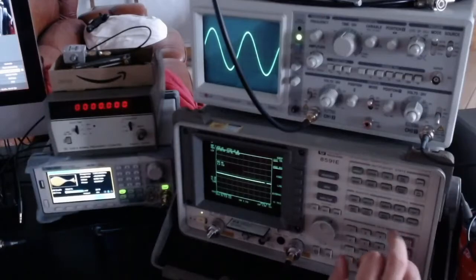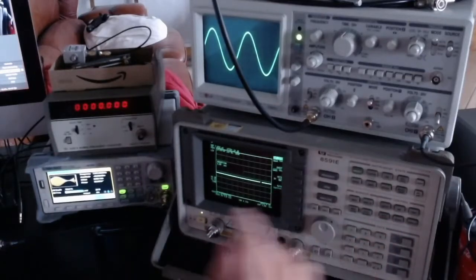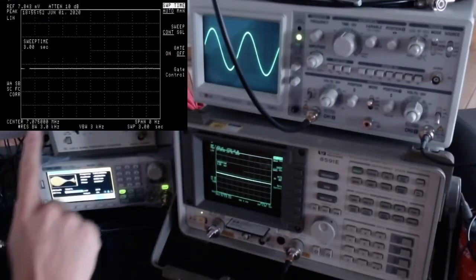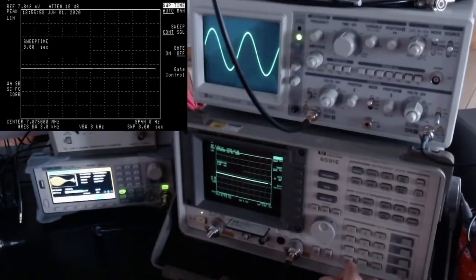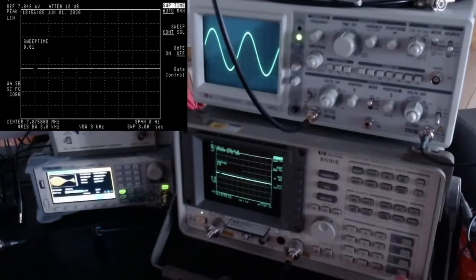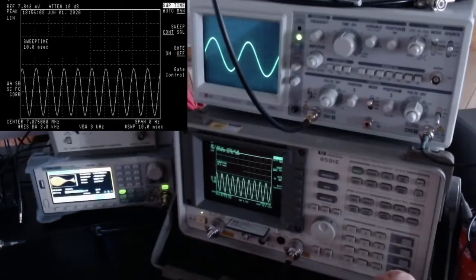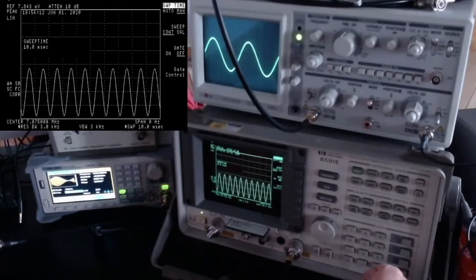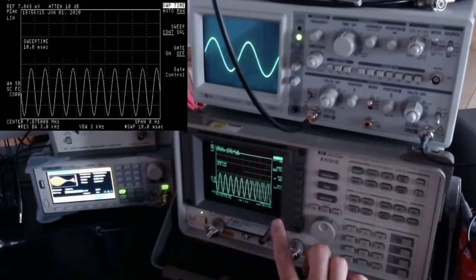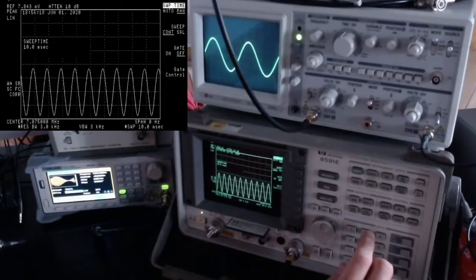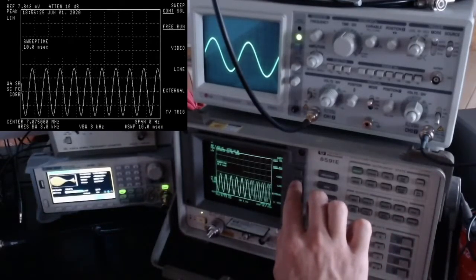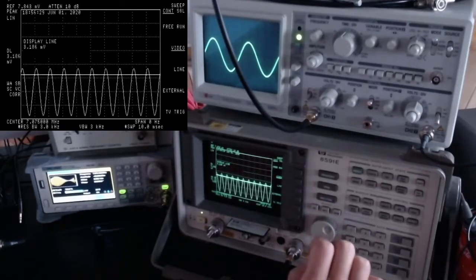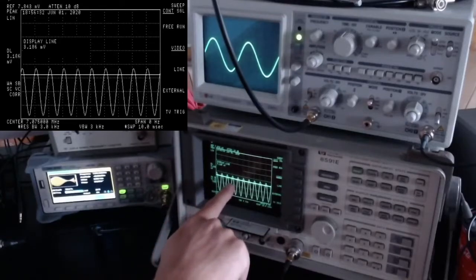Let me change the sweep time. At the moment it's set to three seconds — let me set it to 0.01 seconds, or 10 milliseconds. Now we are visualizing the same information directly on the spectrum analyzer. Going into the trigger menu, I can choose the precise trigger point, giving us stable, readable information.